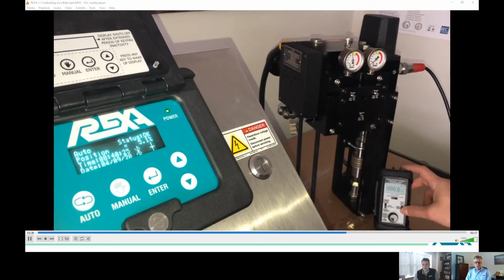The actuator moves away as soon as the control signal changes, and it goes precisely. We can see between 0 and 2.5%, and then 100% back down to 0. As it comes to the seated position, it's building up the hydraulic pressure at position 0. Nice. Oh, it can make very small step changes also.